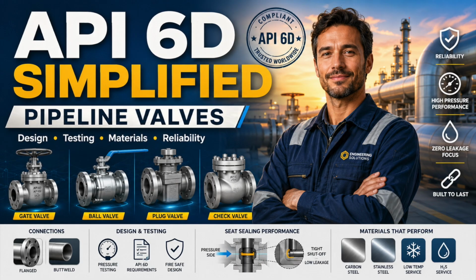A seal may perform in dry gas and fail in aromatic condensate. An elastomer may swell in one fluid and shrink in another. A polymer may work at ambient temperature and become brittle at low temperature. Rapid gas decompression may damage seals after depressurization. The body can remain intact while the sealing system fails.